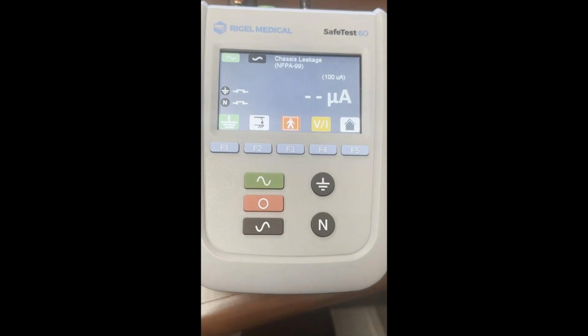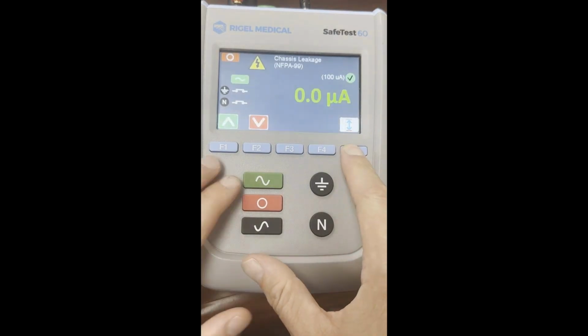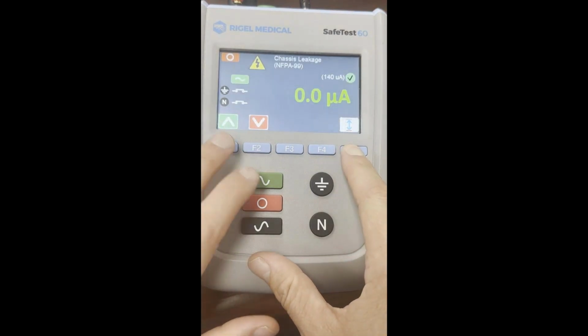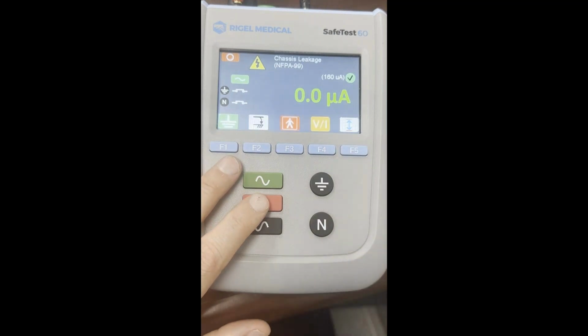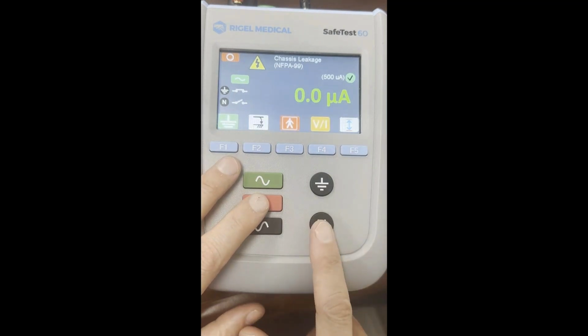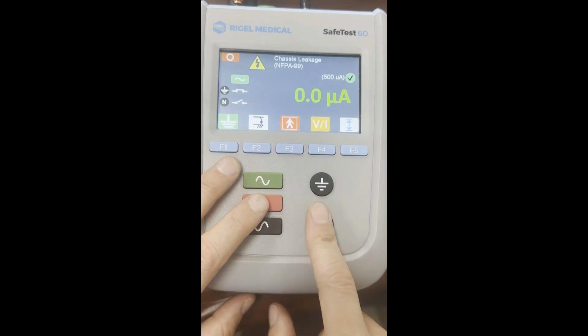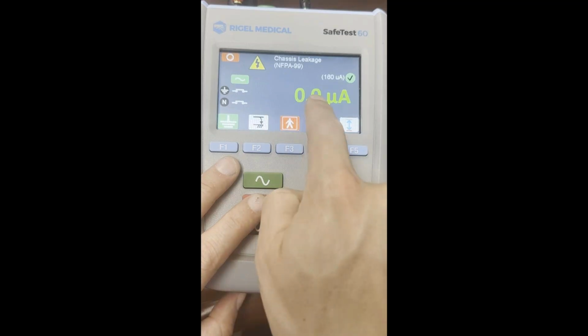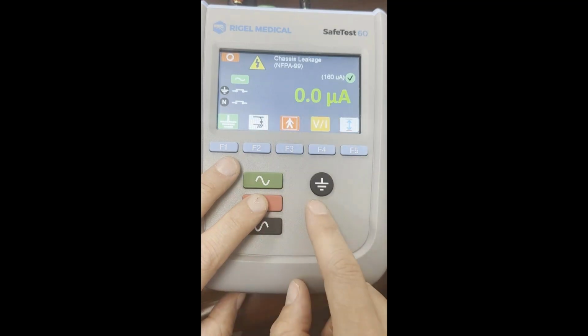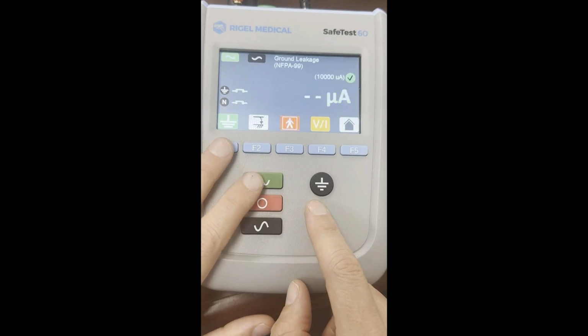So leakage is selected by F2. Hit the green button to activate the device under test. And then we open the ground by hitting the ground icon. Now here you can see I can change the limits. When I open the ground, it goes back to the default 500 microamps, and then it drops down to default. So there are different limits depending on the fault condition.